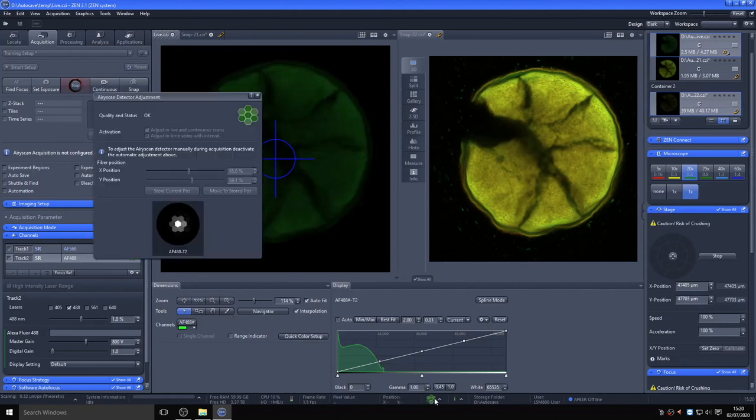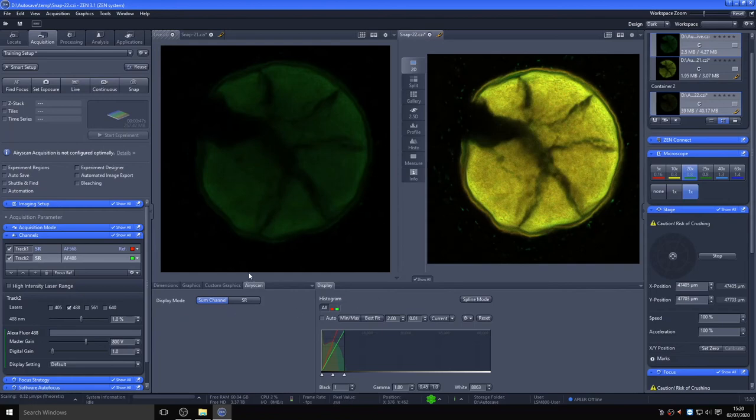Due to little structure, this particular sample is perhaps not the best example of the capabilities of Airyscan, but moving to a higher-magnification lens with better resolution, we should be able to image easily down to less than 200 nanometers. You will notice in the lower portion of the screen that there is a representation of the Airyscan detector indicating its calibration and alignment. This should auto-adjust, but you have the option of centering the image on the central detector using the sliders whilst in live view if the calibration is not optimal. One issue to be aware of with Airyscan is that the file sizes are 30 times larger than normal confocal, even if acquiring the same pixel size, due to the image being collected from 32 detectors as opposed to one, so Airyscan is not advised for general imaging.